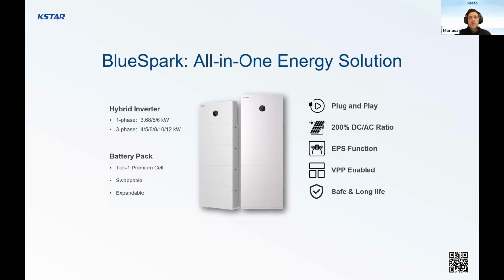So let's say, comparing to the competitors with high voltage solutions with no module level optimization, if one module is faulty or gets unbalanced and you need to replace only one module, it will probably take the whole day because you have to balance the voltages of all the batteries. In our solution, because we are low voltage and optimized from a single battery pack, we can just exchange one battery module. Upselling is also possible thanks to expandable technology. We just add the batteries and they will levelize by themselves by charging up to 100%.